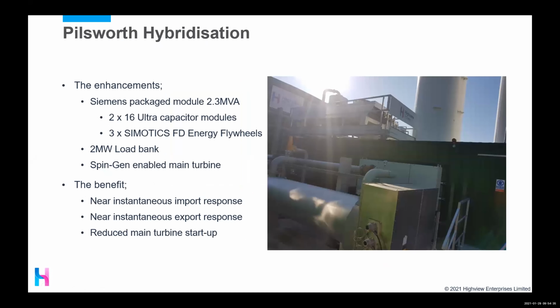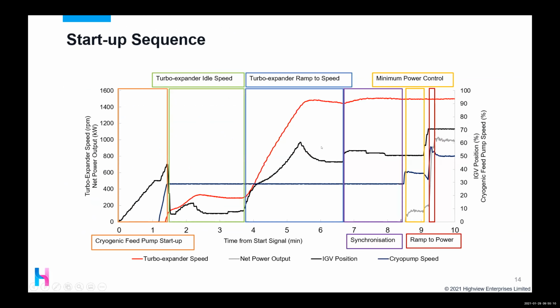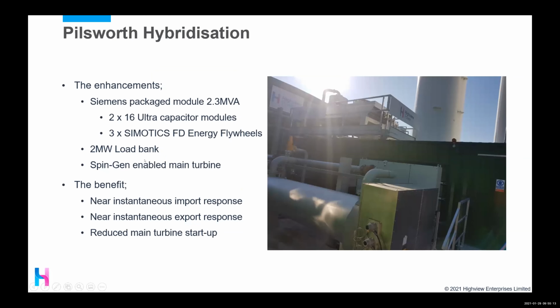So I just want to run through the Pilsworth Hybridisation. So this was the last grant we got to build a very clever piece of kit, which is a number of enhancements to our system. So one is just a way in which we ran our turbine and generator. SpinGen is a name we've robbed from the pumped hydro power industry, where you basically motor your generator. So you absorb power from the grid to be motoring, and this allows you to motor your turbine. The benefit of this is that a number of the steps that we had to undertake here for synchronization can be bypassed because we already are synchronized.